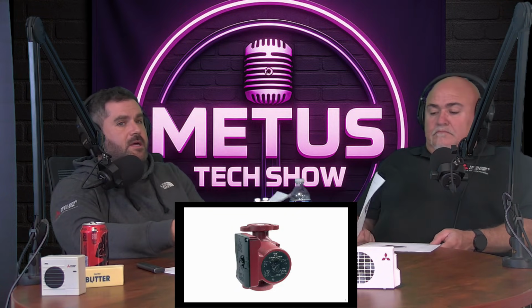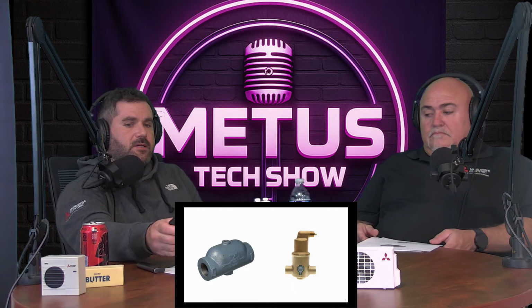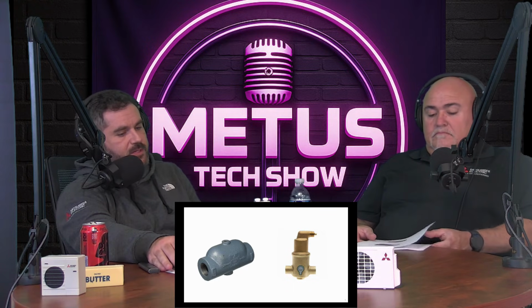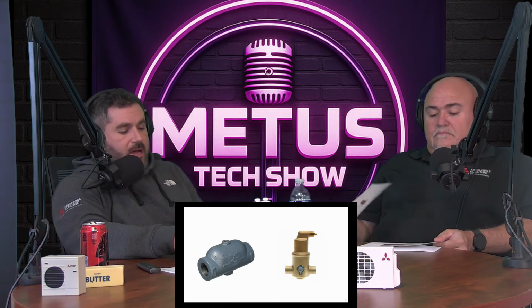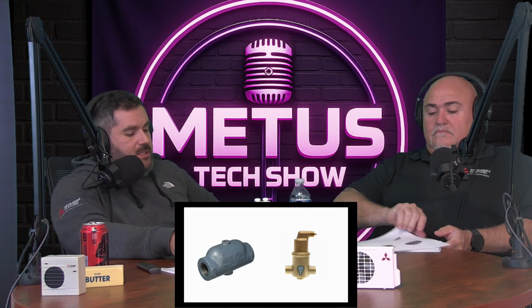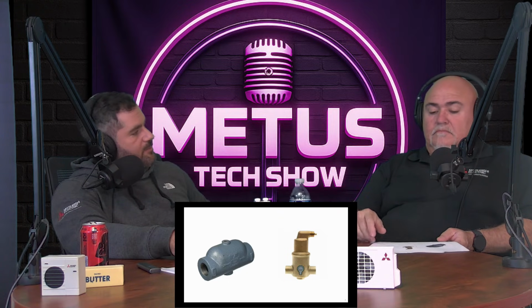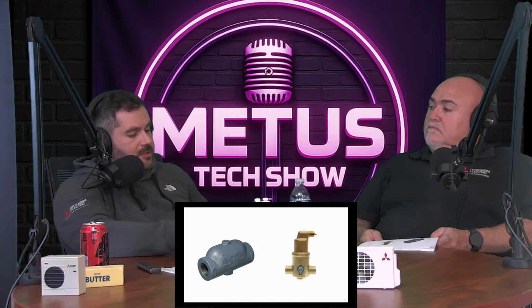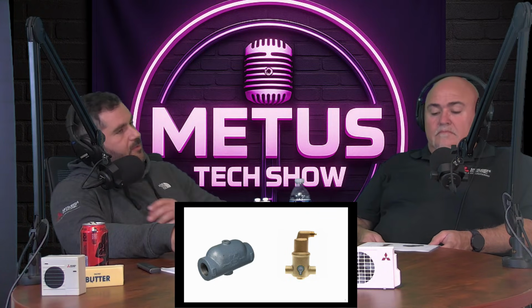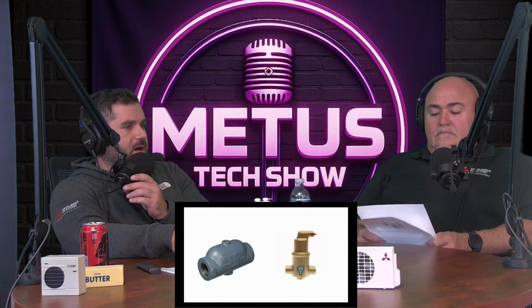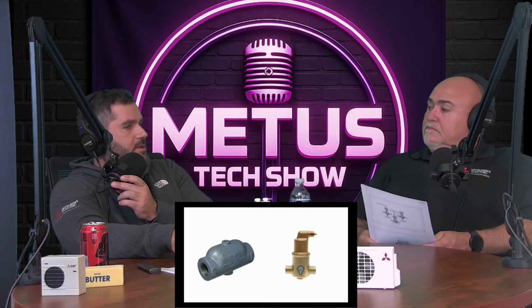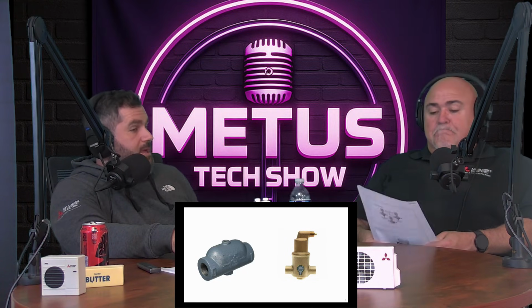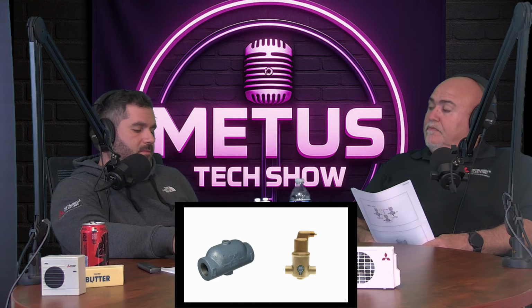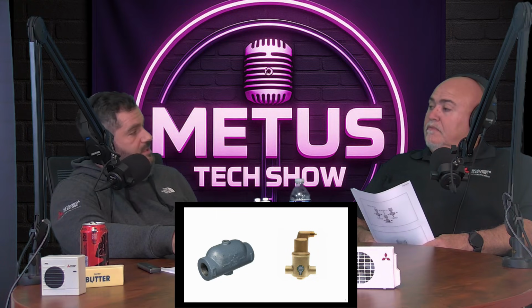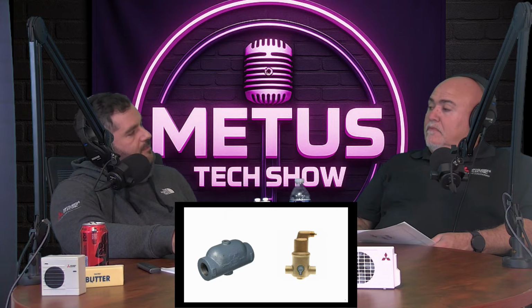All right. Next, we've got air eliminators. So two different types. The one that I got really used to working on is the air scoop that Amtrol makes. It's got the little 1/4-inch port on the top, and then it's got the 3/4 off the bottom, or sometimes 1/2 off the bottom. And that was for typically where you'd put your expansion tank. Yep. And maybe even feed the system with it. But at the end of the day, these are just there to remove small amounts of air from the system.